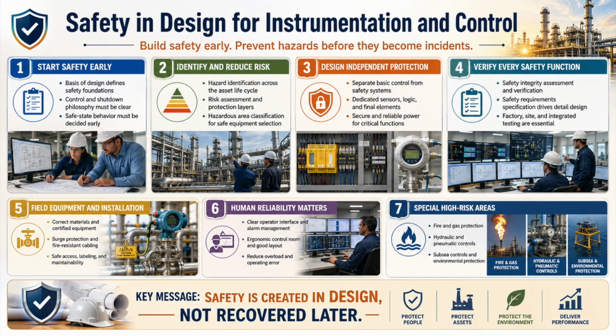Hazardous area design requires more than purchasing certified equipment. Certification must match the gas group, temperature class, protection method, area classification, installation method, cable entry, ambient rating, and local legal acceptance. The complete hazardous area record must remain controlled throughout the life of the facility. An expired, restricted, or incorrectly applied certificate can invalidate an otherwise capable instrument. Measurement design also carries containment risk.